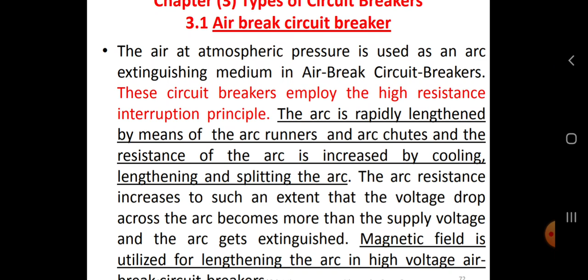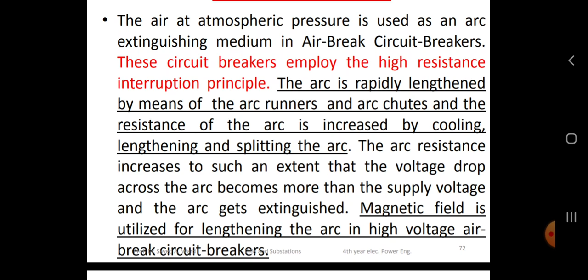The arc is rapidly lengthened by means of the arc runner and the arc chutes, and the resistance of the arc is increased by cooling, lengthening, and splitting the arc. The arc resistance is increased to such an extent that the voltage drop across the arc becomes more than the supply voltage, and the arc gets extinguished. A magnetic field is utilized for the lengthening of the arc in high voltage air circuit breakers. Air circuit breakers are used in DC and AC circuits up to 12 kV.